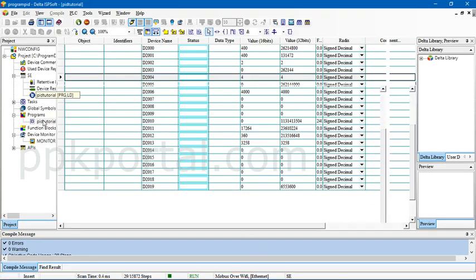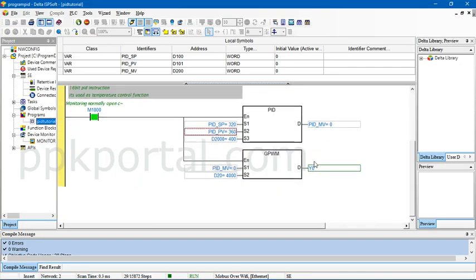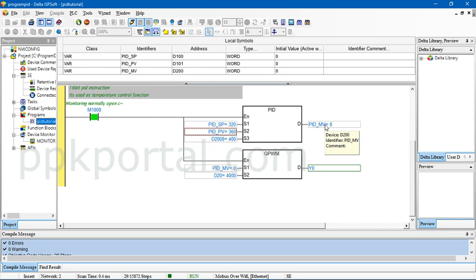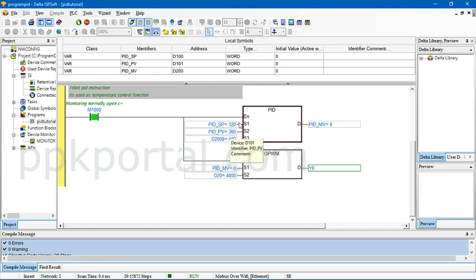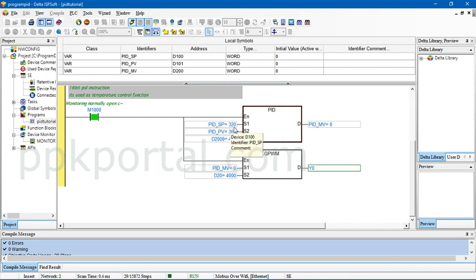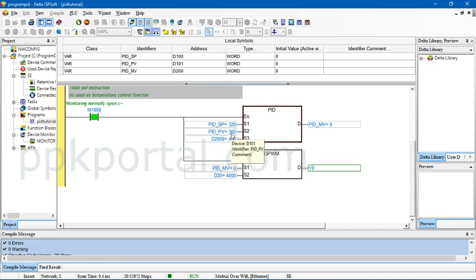Looking at the program, this is your pulse output if you are using SSR. You will be using this digital output. If you have some kind of boiler or control in which you have an analog valve for steam or heating control, you need the analog output. In that case you can use the manipulated variable, you can scale it if you want. It's not necessary that it should be in this range because you can even give 0 to 8000 range or 0 to 4000, whatever range you need. All the Delta modules like DVP04TCS or 04PTS or 06PTS, all these temperature modules give readings like this.